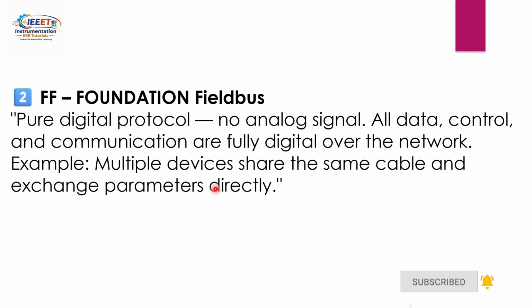Now coming to Foundation Fieldbus. It is a pure digital protocol, no analog signal. All data, control and communication are fully digital over the network. For example, multiple devices share the same cable and exchange parameters directly. The advantage is if you want to transmit a signal from field to DCS or some other system, you need only one pair of wires to transmit the signal. That is the beauty of Foundation Fieldbus.